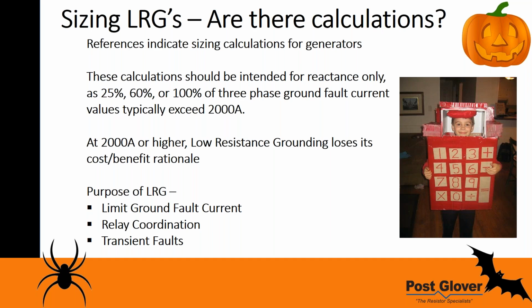But that's really losing the point of what a neutral grounding resistor or low resistance ground is all about. You really want to limit the ground fault current, assist with relay coordination, and maybe ride through some transient faults. Those are the things I think of with low resistance ground.